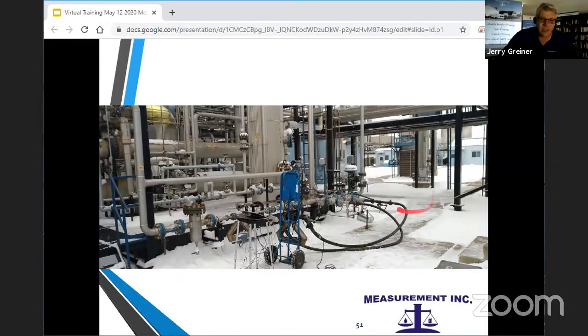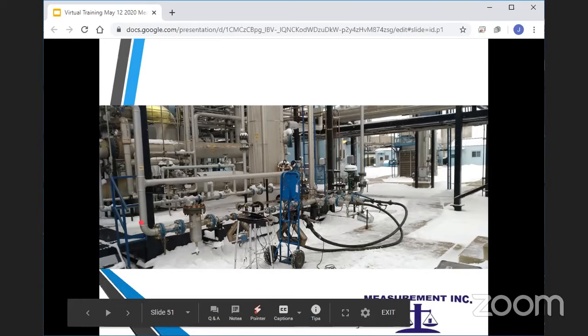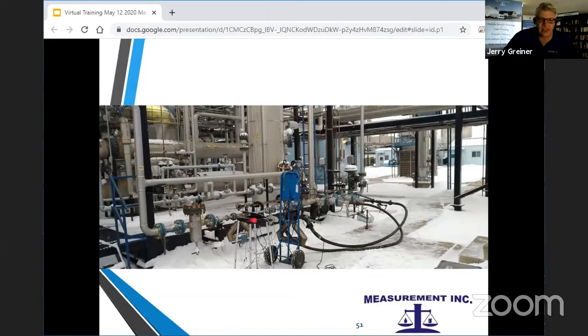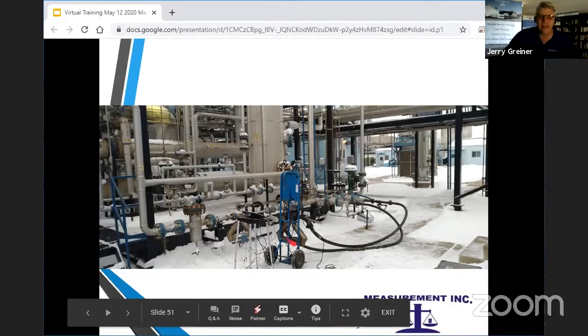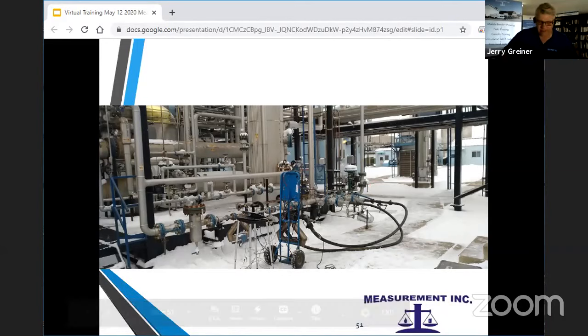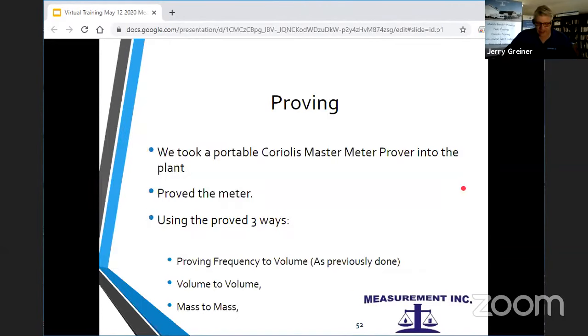So this meter, if you can see it, the flow comes out of a line down here through the meter. Their Coriolis is on there. Down the end, it went through our meter in the middle of the plant and then out. So that's the way we tied into this meter, and it worked very well as far as our proof. When we did it, we proved the meter because we were worried that there were issues on this meter. So we wanted to make sure that we could prove it.